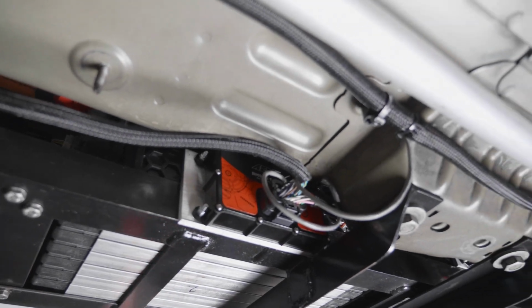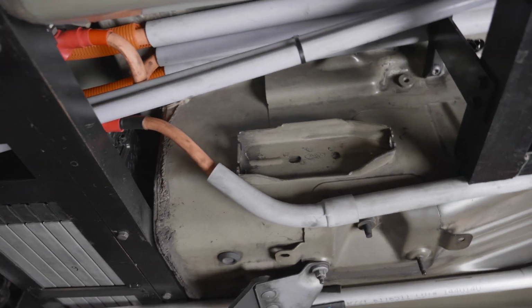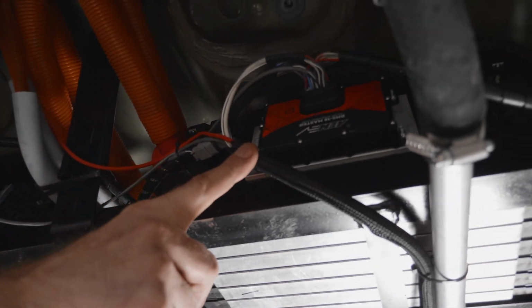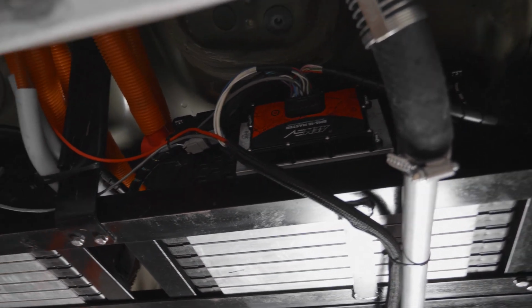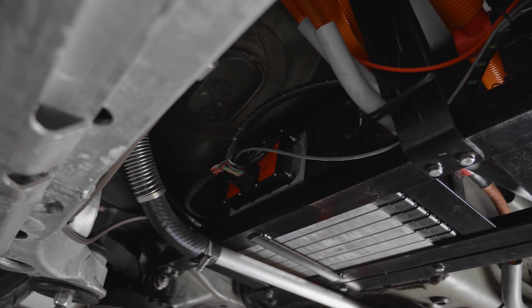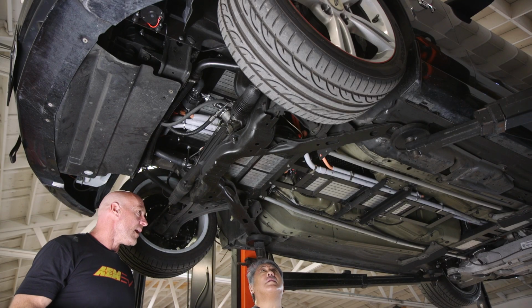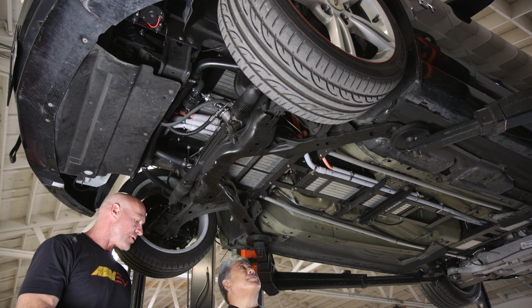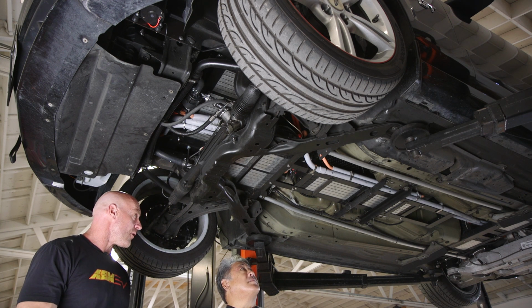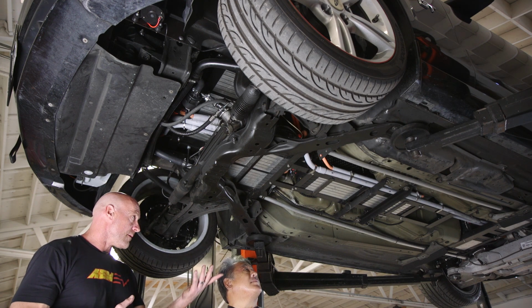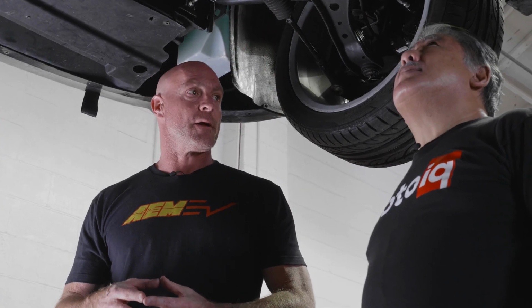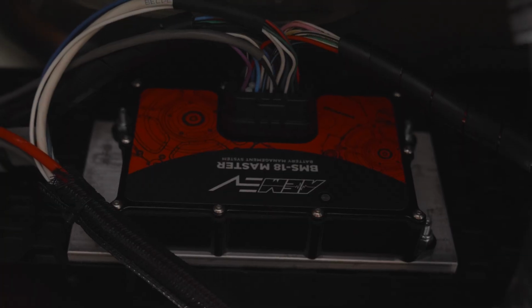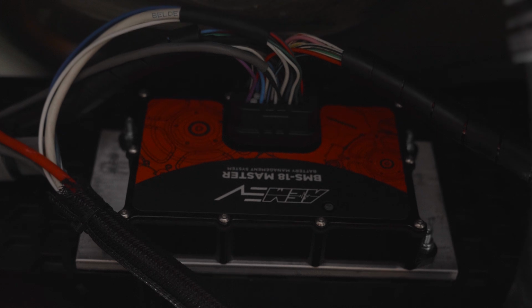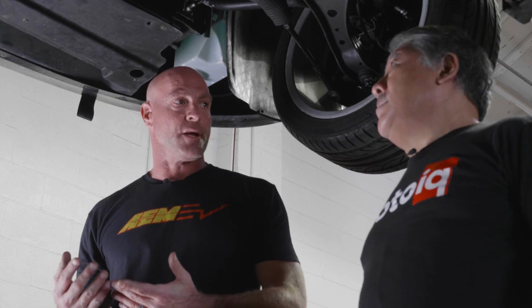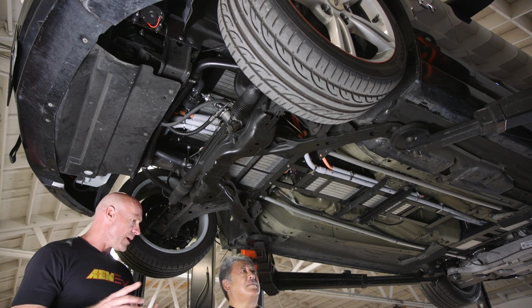It does exactly what it sounds like. It monitors every individual cell in the battery system, and reports all of those values back to the VCU so it knows what to do with it. Why does that matter? Temperature, discharge, current state of charge, all of those things. Because temperature plays a really important role, each one of our modules has 3 thermistors. We call it the BMS, 18 cell taps with 3 temp sensors built into each one. There's a master, and you daisy chain satellites to the master, and the master sends all that data back.